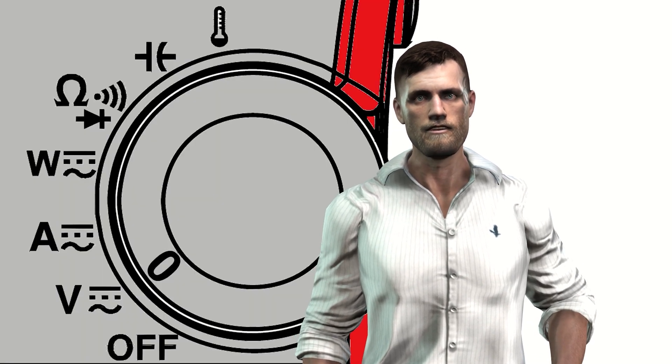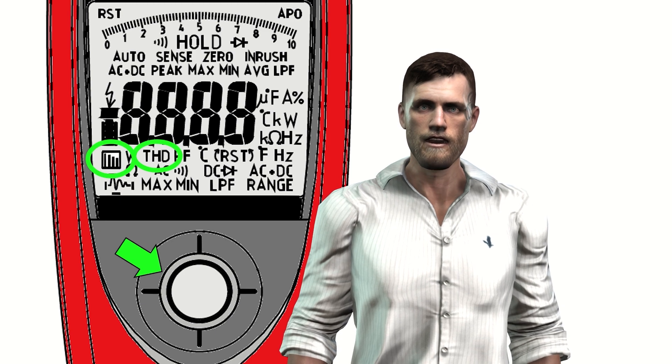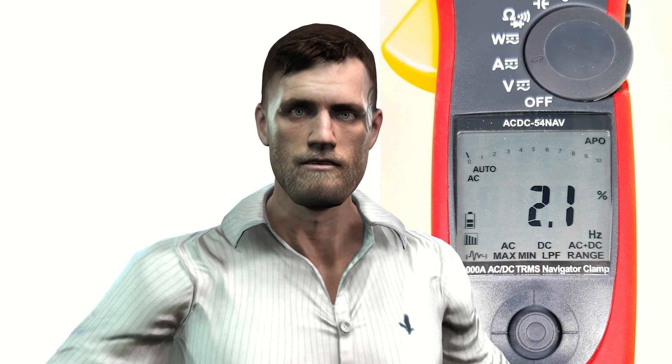To do this, simply move the rotary knob to the voltage or current position. Then we can select with the joystick below the display the THD icon or the harmonic spectrum icon. When selecting the THD option, the clamp will measure the total harmonic distortion, calculated by dividing the effective value of the set of harmonics from order 2 to 25 by the effective value of the fundamental component, and then multiplying the result by 100 to get a percentage value. We can measure voltage THD when the rotary knob is in the voltage measurement position, or current THD in the current measurement position. For voltage THD, the European standard EN 50160 indicates that the value should be less than 8%. For current THD, there are standards for different types of loads such as power supplies, rectifiers, UPSs, etc. In any case, the lower this value, the better for the installation.